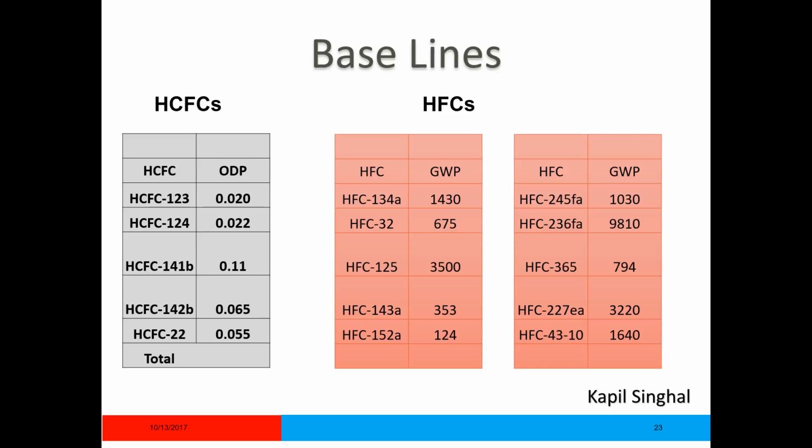It is also produced in India. There is one refrigerant gas production facility which I know of that is also producing it in India, whereas R-32 is right now being considered as an alternative, but it still has a GWP of 675. So probably it will be there in the baseline, and we need to see for how long we can continue to use 32, because this is still considered to be higher GWP, and we may have to cut down on its use eventually.